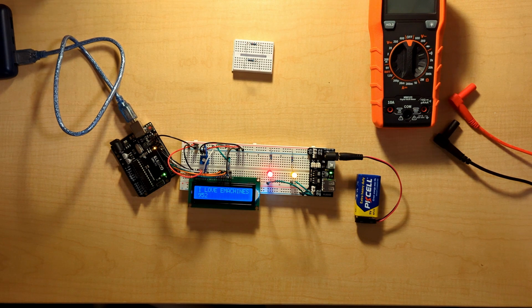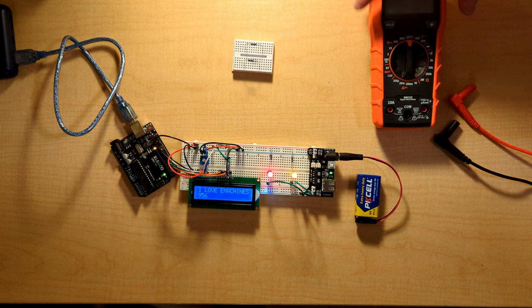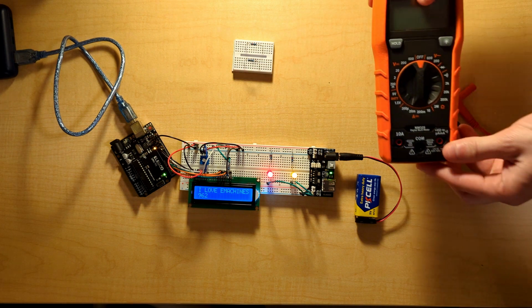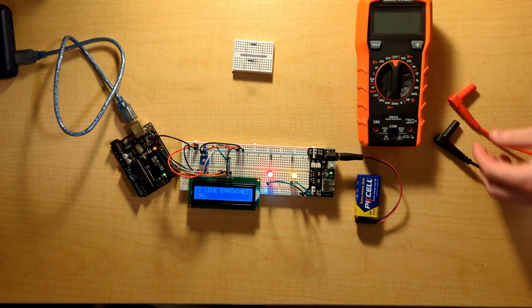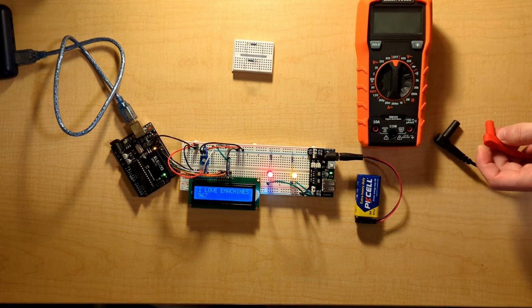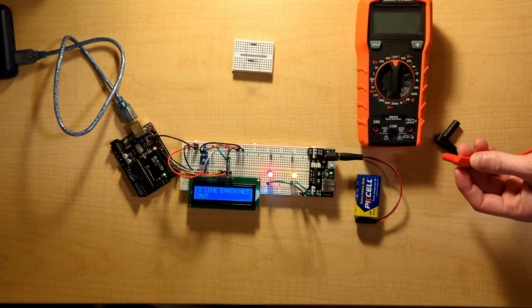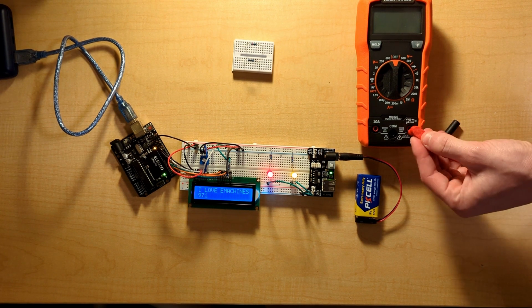As far as safety precautions are concerned with the digital multimeter, one of the most important things to consider is the overall condition of the meter. Just give it a good once over to make sure there's nothing exposed, no damaged parts of the meter before you start using it. Furthermore, it's also important to ensure you have a proper connection between your test leads and these ports here on the meter.